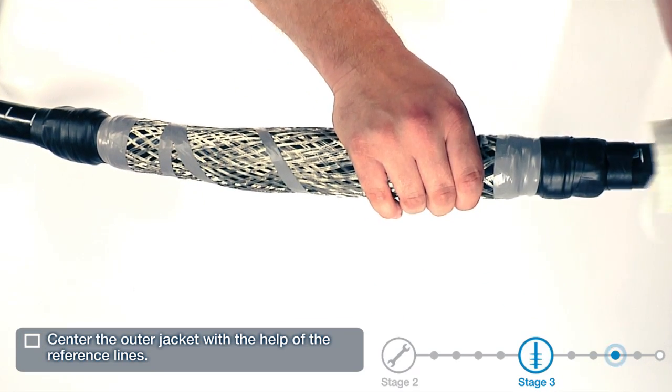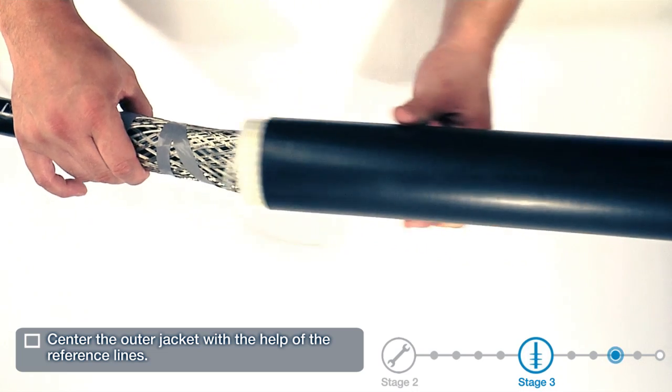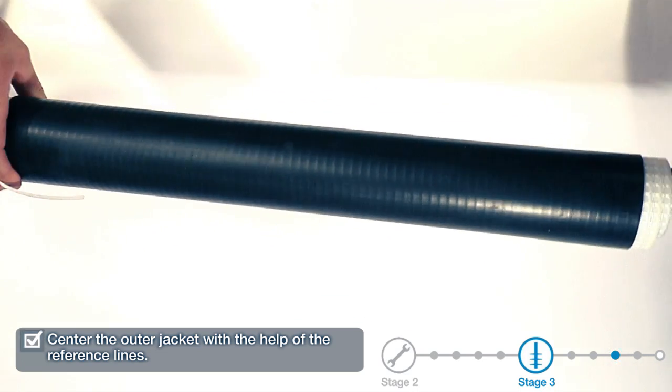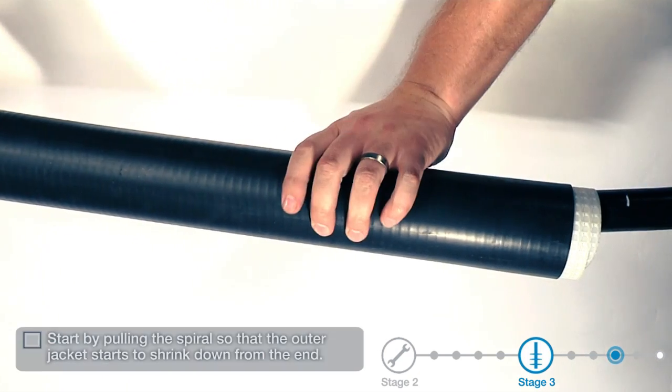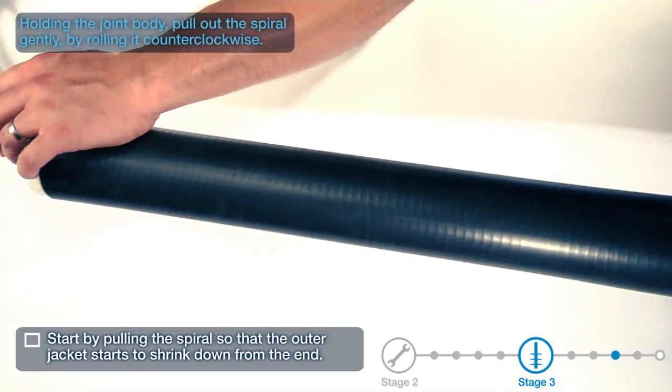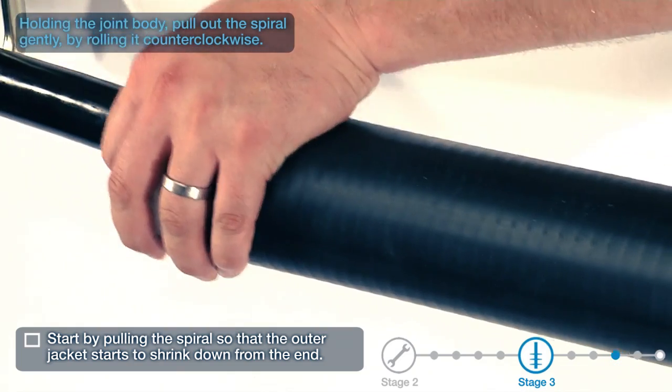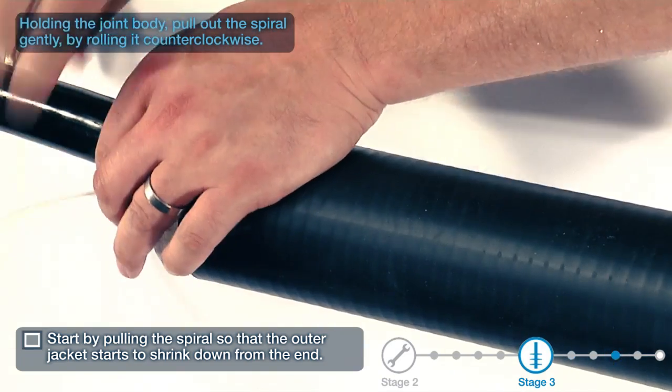Center the outer jacket with the help of the reference lines. Start by pulling the spiral so that the outer jacket starts to shrink down from the end. Holding the joint body, pull out the spiral gently by rolling it counterclockwise.